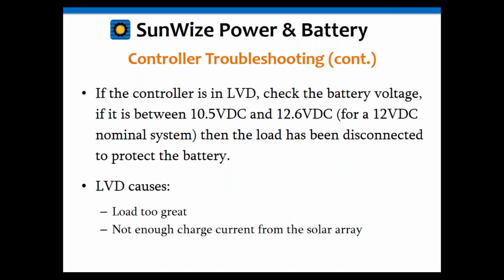So again, going back to the controller, if you find the controller is in LVD and your battery voltage is low, for a 12-volt battery somewhere between 10.5 and 12.6, then the load's been disconnected. Usually the first way you find out you have a problem with your system is the load's gone down. So you get out there and you might see from the LEDs on your charge controller and from your multimeter that yes, the battery is low and that the charge controller disconnected the load to protect the batteries from being over-discharged.